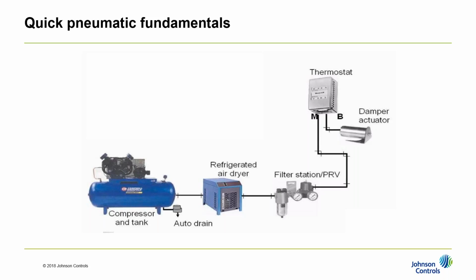In today's discussion, our controlling device is going to be a thermostat. The thermostat is going to regulate that mainline pressure to a branch line pressure, and it's going to use a bimetallic strip that bends depending on the temperature and controls what that branch line pressure is going to be.